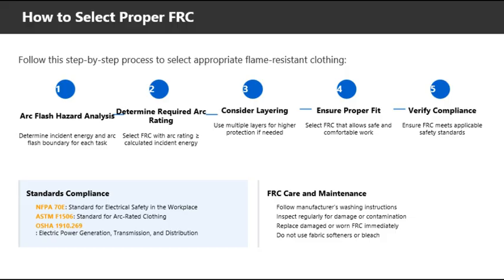Now let's walk through the step-by-step process for selecting proper flame-resistant clothing. This systematic approach ensures you get the right protection for your specific work environment. Step 1. Conduct an arc flash hazard analysis. This engineering study determines the incident energy and arc flash boundary for each piece of equipment and each task you'll be performing. Without this analysis, you're essentially guessing at what protection you need.